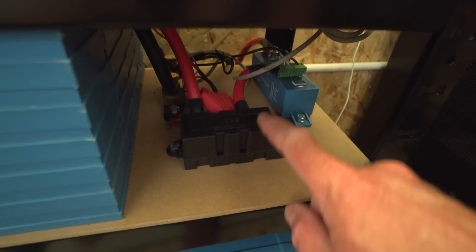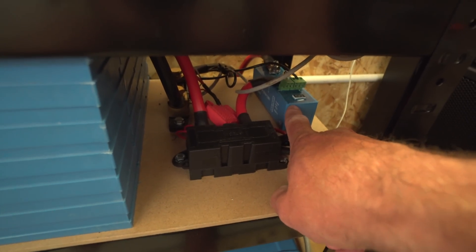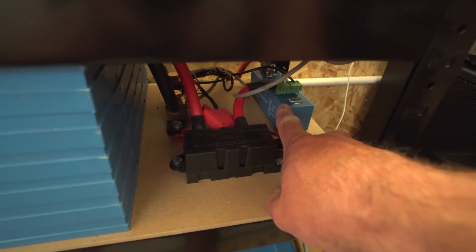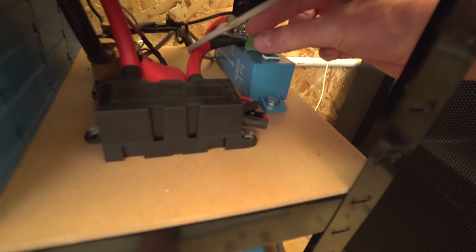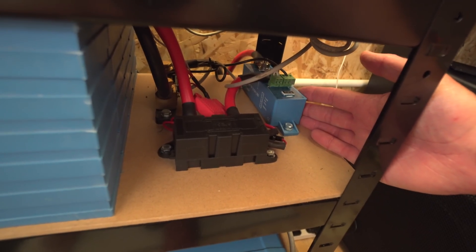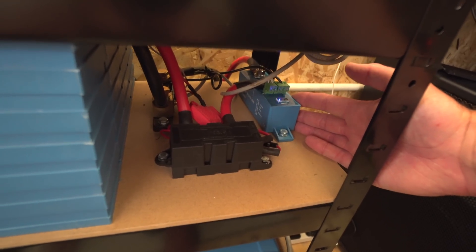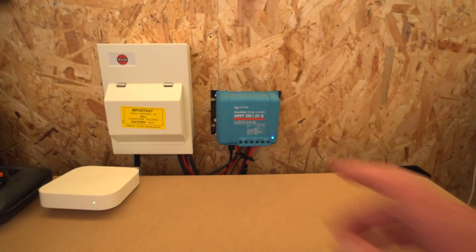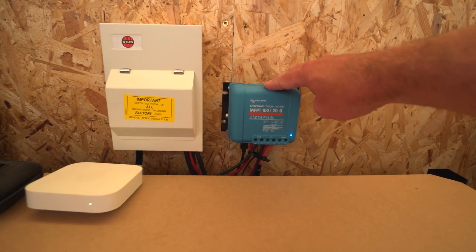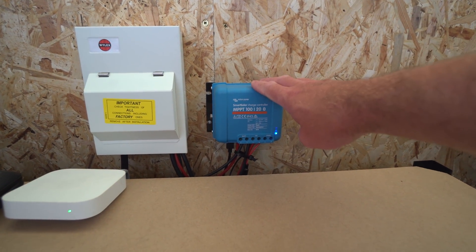Because it's on that battery meter, it allows you to monitor it remotely, which I'll show you in a minute. This is all wired up with nice hefty cable. We've got a 200 amp fuse here, and a Victron Battery Protect which lets you remotely turn the system on and off. You can also disarm everything by removing this little jumper. It's a good way of shutting things off if the voltage gets too low. In there is also the shunt for the battery meter.